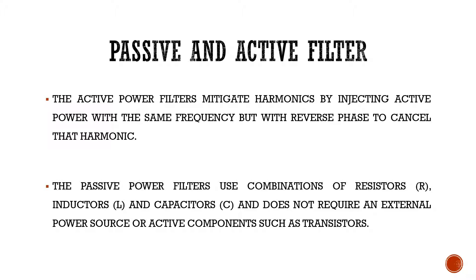The active power filter is one of the most commonly used filters for harmonic compensation in industries. It is capable of mitigating the harmonic present in the system by injecting an active power with a reverse phase, so that it cancels off the harmonic component already present in the system due to the non-linear loads connected. Whereas the passive filter uses a combination of resistor, inductor and capacitor, and does not involve any active components such as transistors. But it cannot give a dynamic compensation of harmonics.